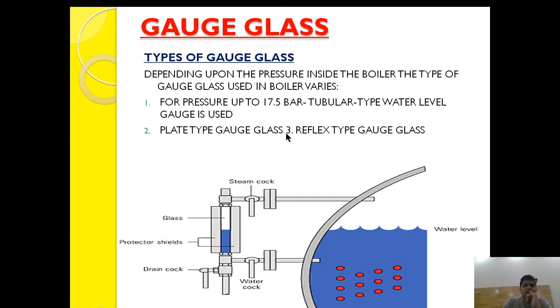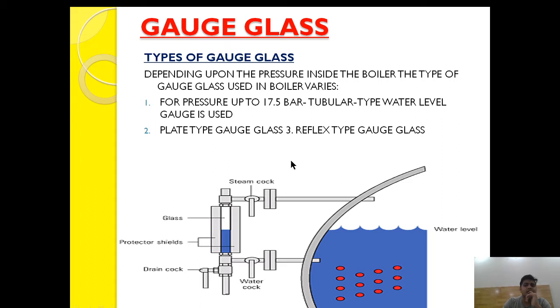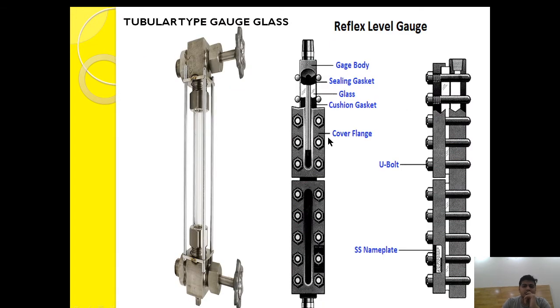For higher pressure ranges, the plate type gauge glass and reflex type gauge glass came into the picture. The reflex type gauge glass is used from medium to high pressure range, and the plate type gauge glass can be used in all types of boilers — medium, high — because the pressure range of the plate type gauge glass is around 70 bar, and the reflex type gauge glass pressure range is around 21 bar.